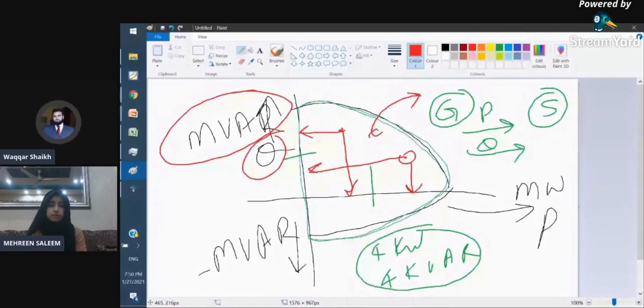Whenever this situation comes, it is called the overexcitation situation of the generator, where we are drawing more reactive power than the acceptable limit. If you are crossing this range, this is your overloading. If you are going above this range, outside this curve, you are going into the overexcitation region, where your generator cannot supply that much reactive power which you are trying to draw from it. So there are three concepts: overloading, overexcitation, and underexcitation.